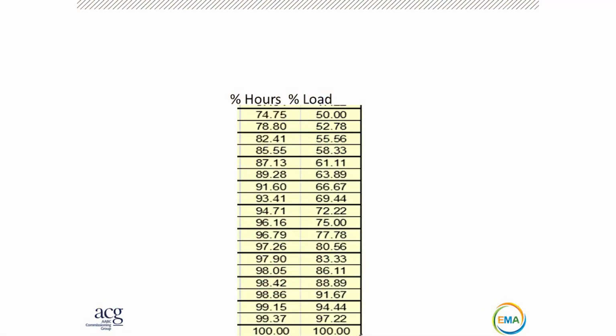The very bottom of this chart is 100%. So what that's saying is, on the far right column, 100% of load happens when it's like -5 out. And as it gets warmer, as we go up on the chart, the load shrinks, right? The column on the left is the percentage of total operating hours cumulative. So if we look at the very top, 50% of the load. So when the building only needs half of the design capability, it's about 75% of the total hours in the heating season. So 3/4 of your heating season, the load is 50% or less. That's the majority of the heating hours, right?